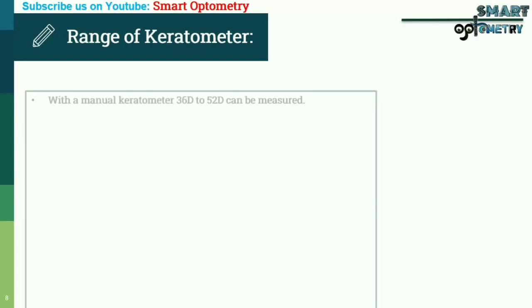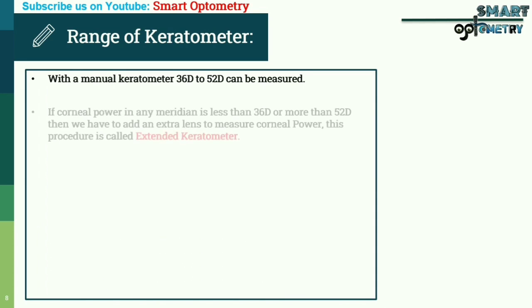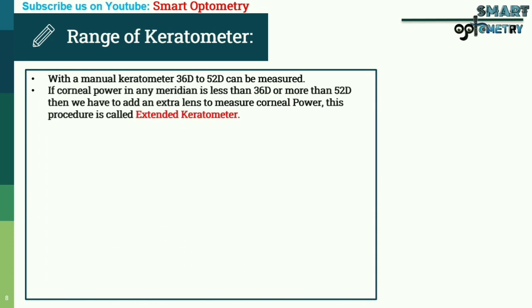The range of a manual keratometer is 36 diopters to 52 diopters. If the corneal power in any meridian is less than 36 diopters or more than 52 diopters, then we have to add an extra lens to measure corneal power.